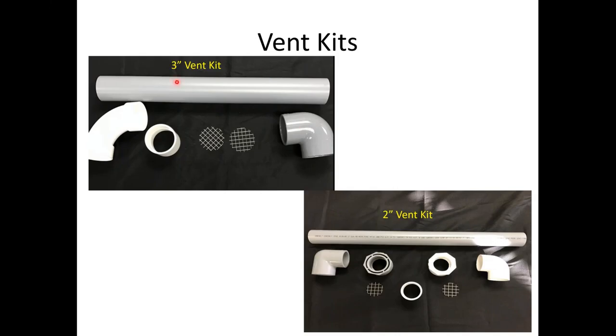But our vent kits, what they will come with, I get your CPVC, your CPVC 90, your 2 stainless vent screens, and your terminations. There is a 2-inch option. The 85 and the 105 on the Raptor can vent in 2-inch. We can go 135 feet in 3-inch. We can go 60 feet with 2-inch. 2-inch is basically going to be the same, except it's going to have the reducers and everything's going to be in 2-inch. The 320, 399, there is a 4-inch kit available for it, but they can also be vented in 3-inch, just at a reduced vent length.